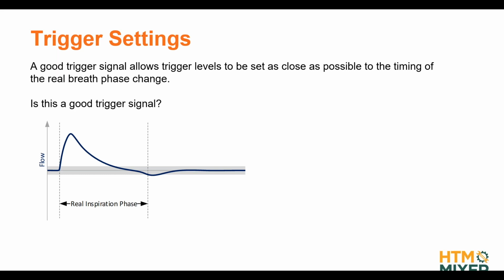So let's have a look at three different signals and judge them for their qualification as a trigger signal. So this is the first one. The gray vertical dashed lines here indicate the actual real breath phase transitions. So here is where an inspiratory phase starts, here is where the expiratory phase starts. So the time in between would be our real inspiration phase. And this gray area here around the zero of this flow curve indicates an area where we don't want to have our trigger levels, because they are so close to zero. If you have a little bit of signal noise, you could have false triggering. So who thinks that this is a good trigger signal? Raise your hand, please. Okay. Who thinks it's a bad trigger signal? Okay. So let's have a look at it together. So you're not quite sure, right?